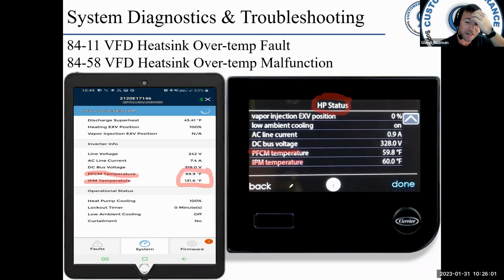These sensors are embedded in the VFD, so it's not like you can put a clamp on there and double check, okay? When the fault's active, the VFD will shut down the compressor, but continue to operate the fan to draw air across the heat sink. Try to expel any residual heat. Once the heat sink temperature is acceptable, the system will restart, but with a reduced demand. Much like the high pressure condition, it's going to reduce demand by 25% for each 8411 occurrence. After you get to the minimum, 25%, and you still have a VFD heat sink over temp fault, then you'll get the 8458, and it will be a lockout, 2 hours.